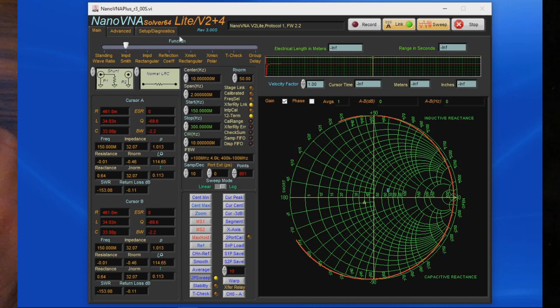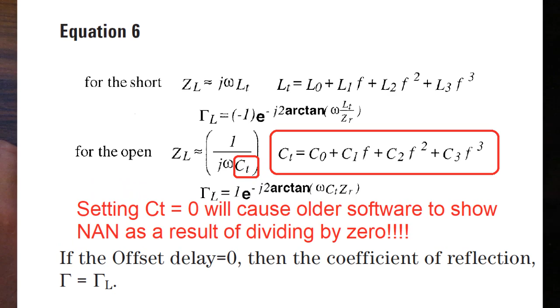Somebody wrote me once saying they'd entered in all their own values for these, and the VNA stopped working -- it stopped displaying data. They had zeroed out this coefficient, and if you look at the math behind this, it causes it to divide by 0. So the reason I've got this 1e to the minus 9 in here was to avoid that divide by 0. With the new software, I add a small offset so we can actually change this to 0 now.